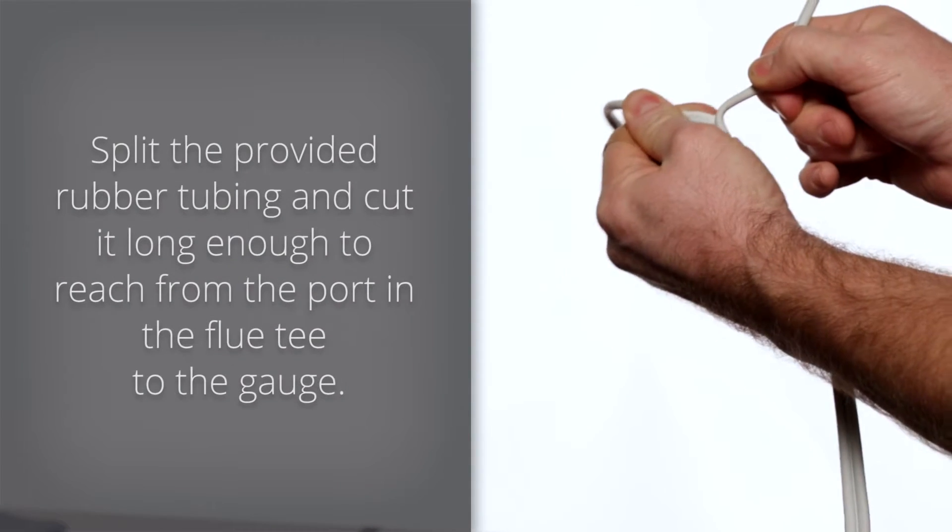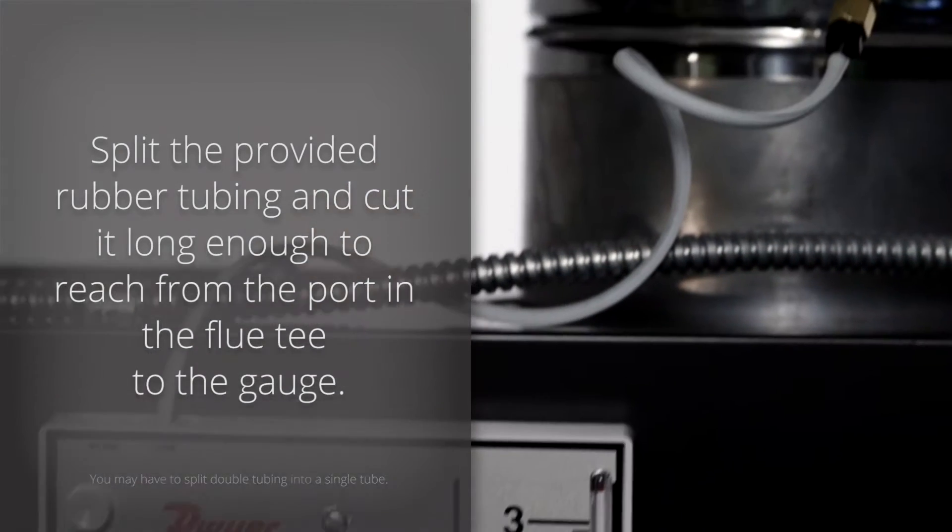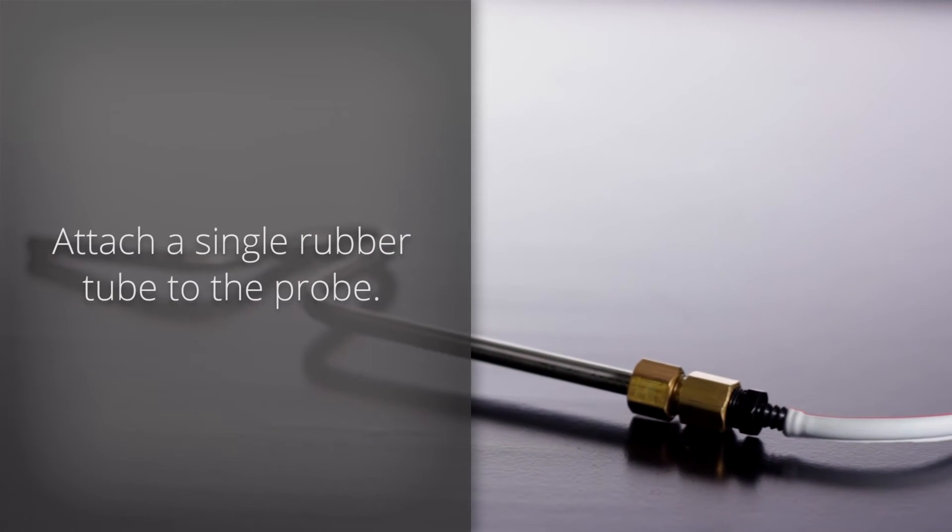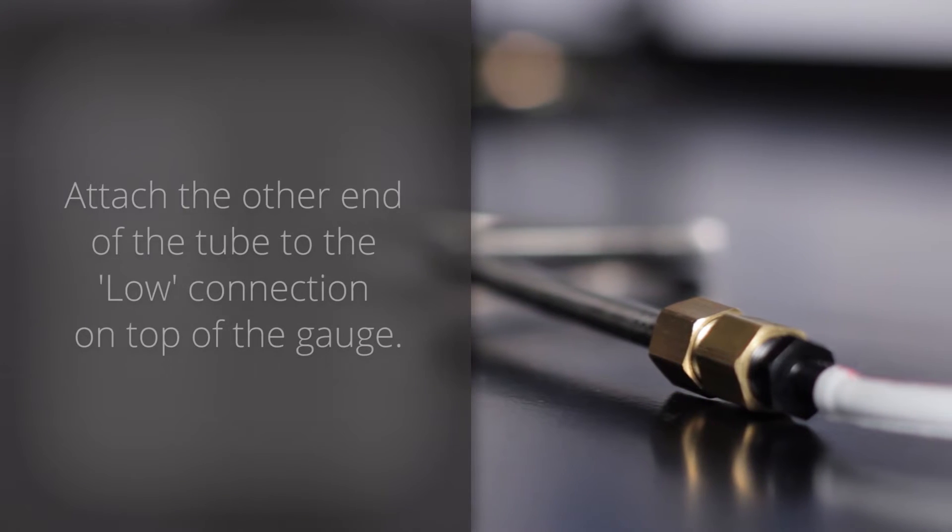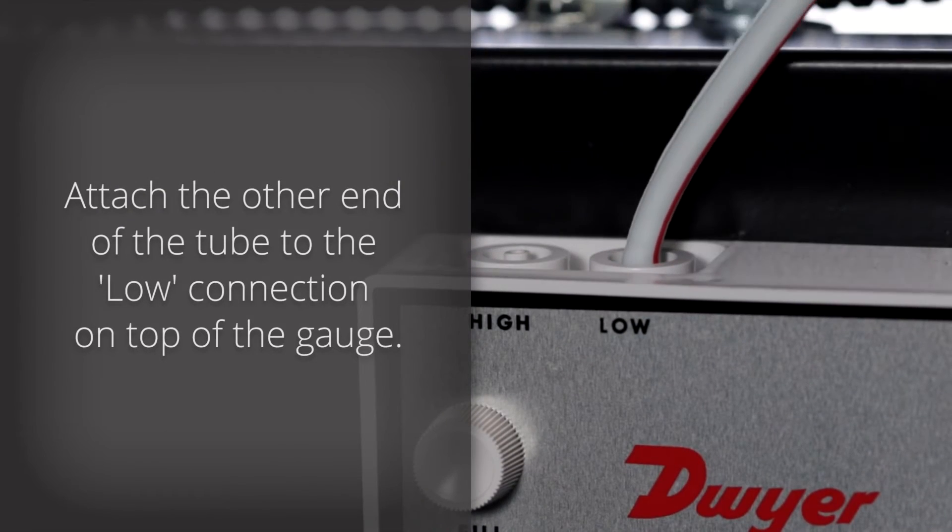Split the provided rubber tubing and cut it long enough to reach from the port in the flue tee to the gauge. Attach a single rubber tube to the probe. Attach the other end of the tube to the low connection on top of the gauge.